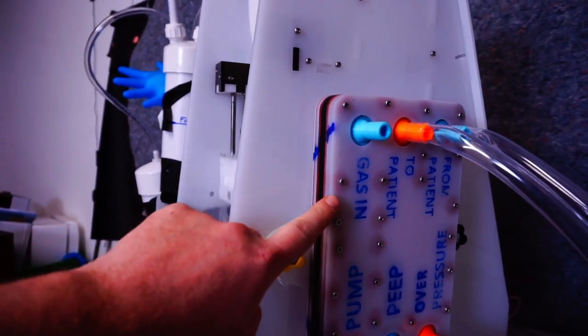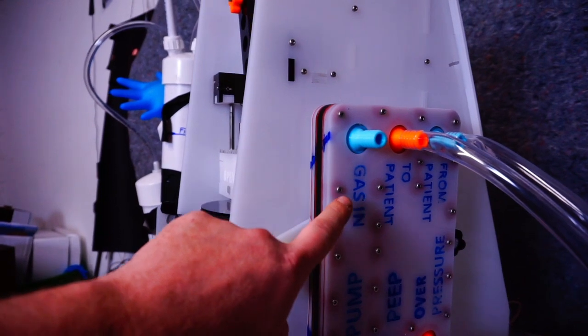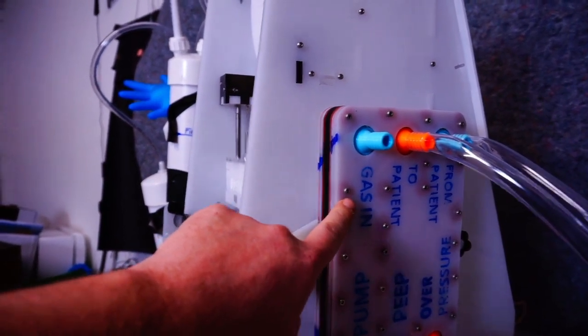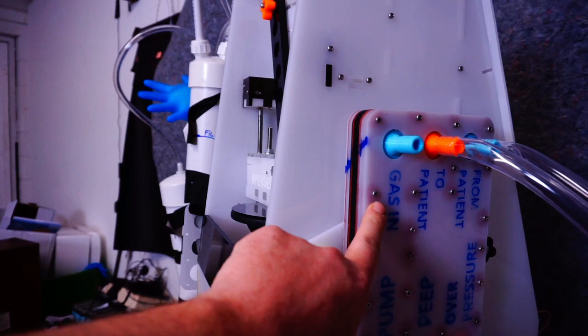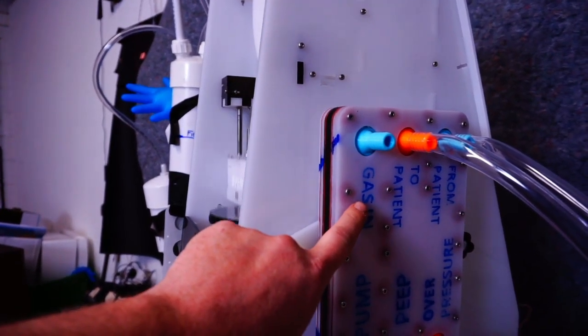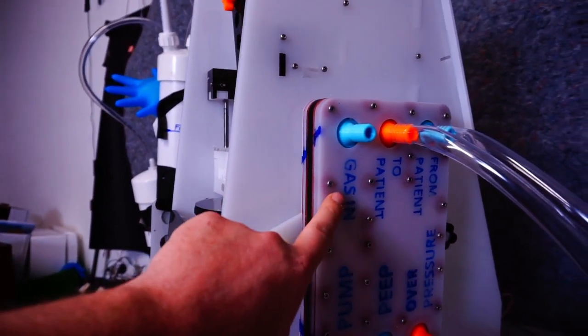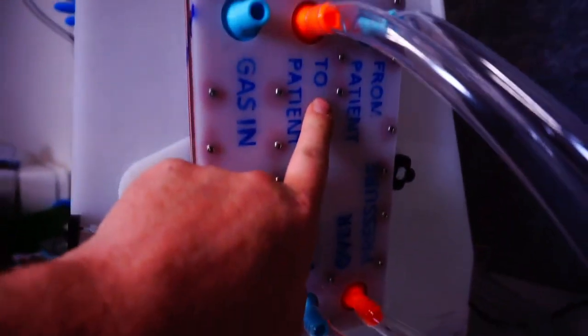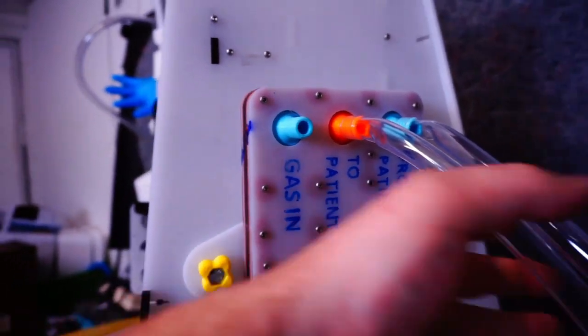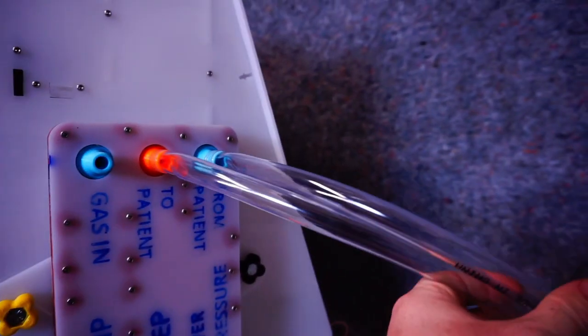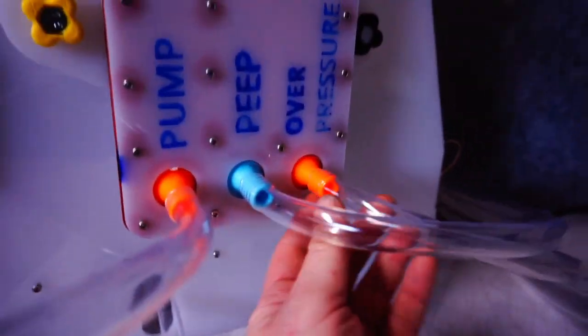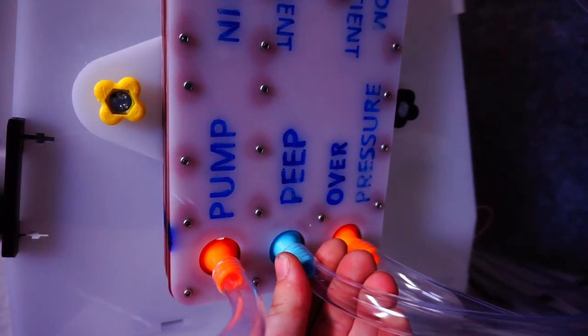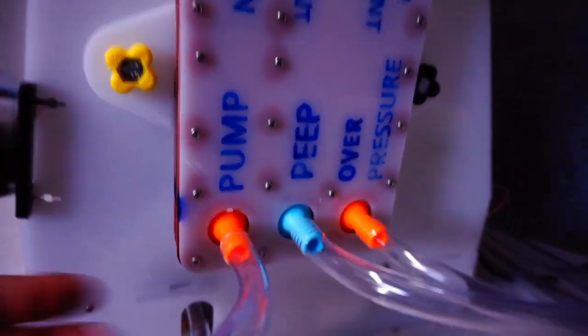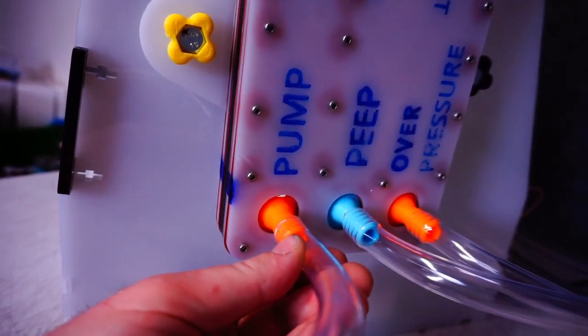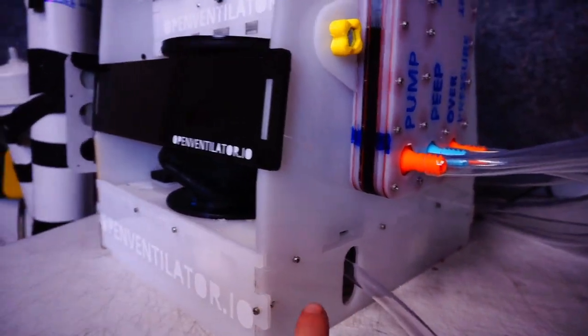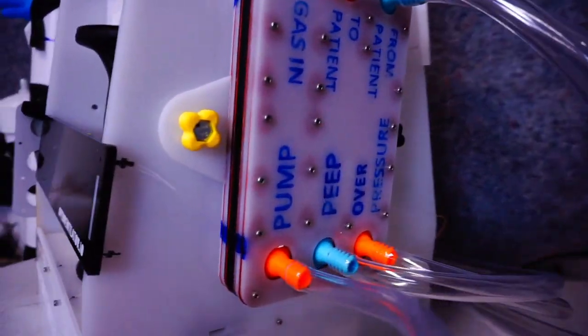There are other open source and crowdsourced projects working on air and oxygen mixing valves that are 3D printable or injection moldable, and they're reasonably common off-the-shelf medical parts. These two ports are to and from patient. That's these guys going to the T at the glove. This port goes to the overpressure. This port goes to the PEEP system. And this goes to the pump. The pump has another tube down under there, which comes out here.